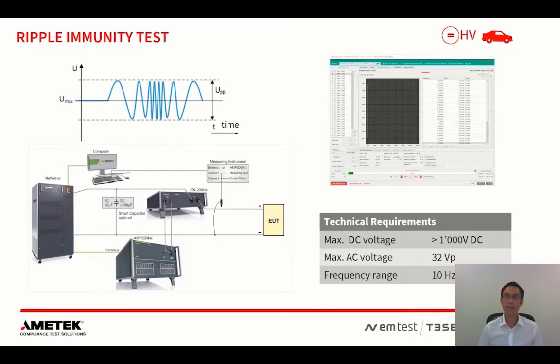So we're simulating here the different current ripple and voltage ripple that might be present on a high voltage DC bus. The test setup consists of a DC source, which you can see here, that's our NetWave, for example, and it consists of a high frequency signal generator plus an amplifier and a coupling device. Usually this is an inductive coupling through a transformer. So in this case, the NetWave source supplies DC to the test object, and the amplifier and the coupling network, which is the ripple generator, generates the ripple on top of the DC. As I said, the maximum requirements are about 30 volt peak, which is the ripple voltage, which might lead to very, very high ripple current depending on the impedance of the test object.